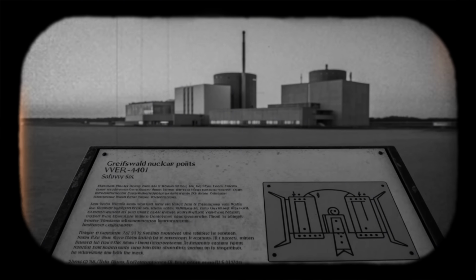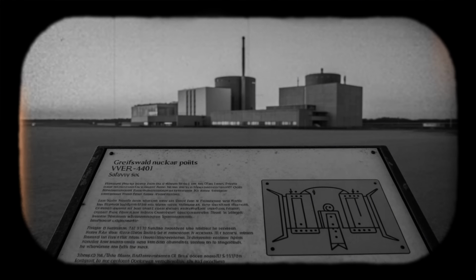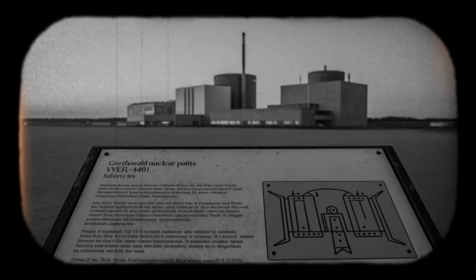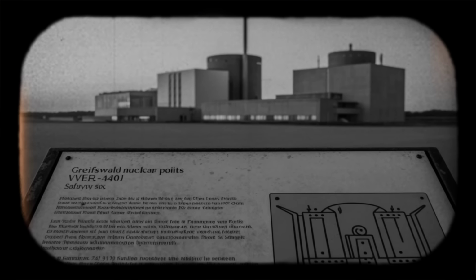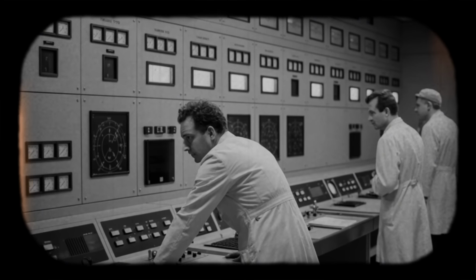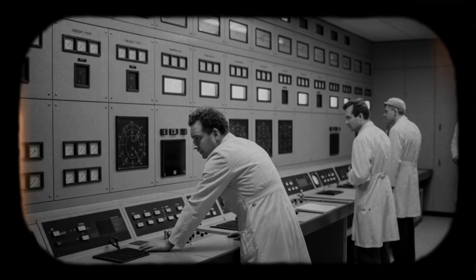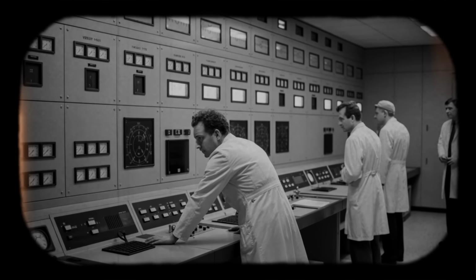The fire burned for approximately 92 minutes, not because the brigade was incompetent, but because the building's geometry and fire protection design constrained their effectiveness. The OECD Fire Database and IAEA experience reports would later use Greifswald as an example of how long-duration fires correlate with more severe cable damage. Fire duration matters. The longer flames and heat persist, the more cables fail, the more systems are affected, the greater the challenge to plant safety.